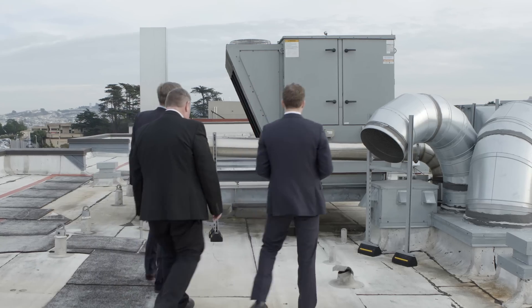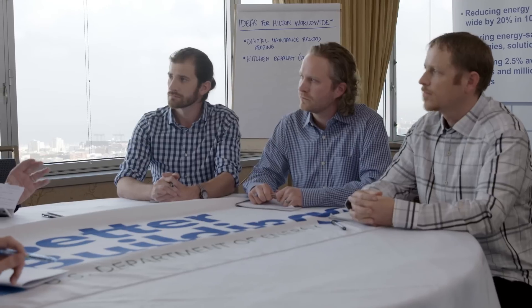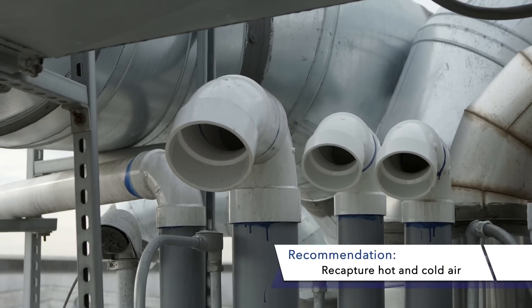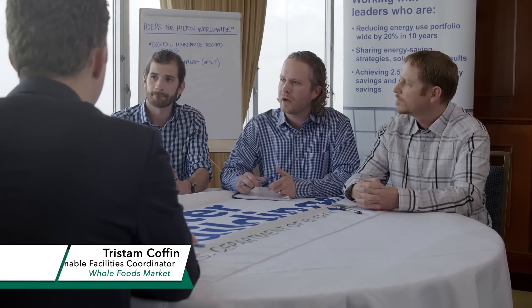When we walked the roof at your place, we noted that the exhaust was direct exhaust. What we've done in some places, we've added a recirc to take that exhaust and then through charcoal filters, put it back into the supply side. They have several hoods coming in, usually with this cold climate that we have here in San Francisco. They could capture some of that heat and preheat the air coming in. And you've done that with Type 1, grease-laden air? You've been able to recirc? Oh, that's great. Fantastic.